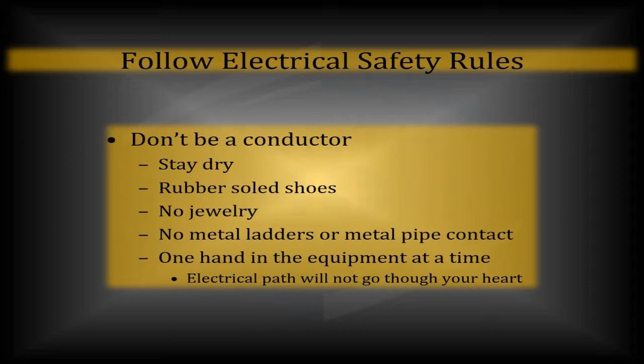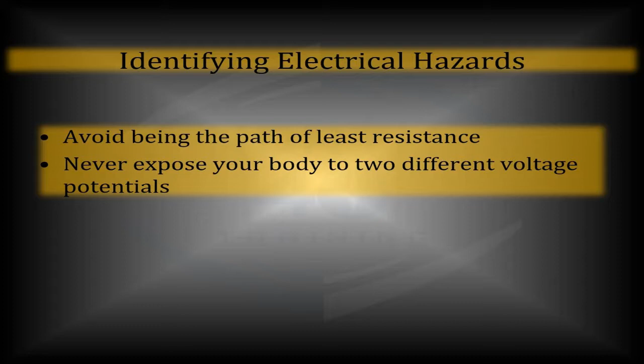Be able to identify those electric hazards. Avoid being the path of least resistance so you don't become any path. Don't expose your body to two different voltage potentials. That can be just as bad as touching a grounded object with your hand on an open wire. If you've got two different voltage potentials, they're going to try to equalize, and if you're the object they can travel through, you're also going to be the object they equalize through.